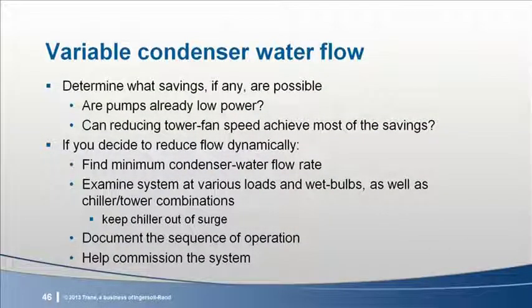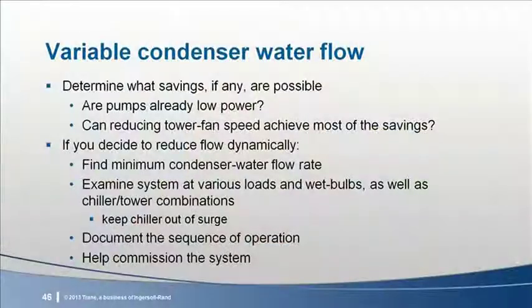As we discussed in the 2011 broadcast, you need to determine whether or not dynamically changing the condenser water flow rate should even be considered. If you've already minimized the condenser water pump kW, for example, by reducing its design flow rate to 1.5 or 2 GPM per ton, it may not even make sense to take the time to look further. The pumps already have a really low contribution to the chiller plant energy picture. If you already have VFDs on your cooling tower, reducing the tower fan speed dynamically can achieve a lot of the potential savings, and it's simpler.